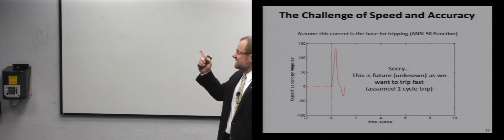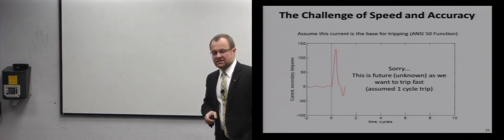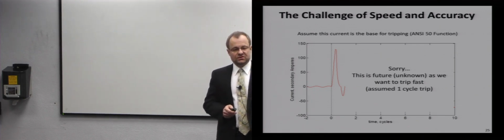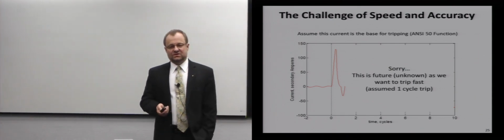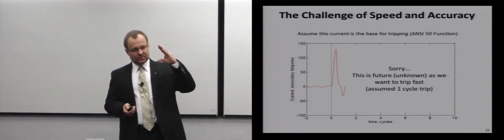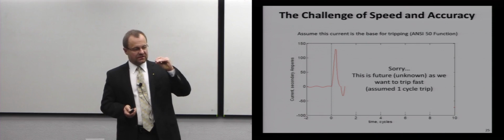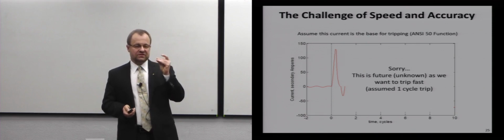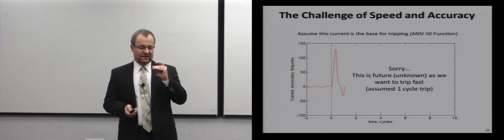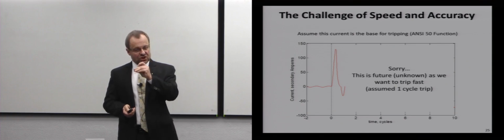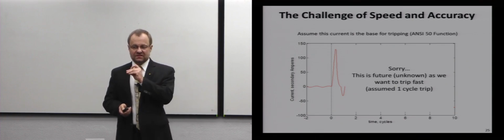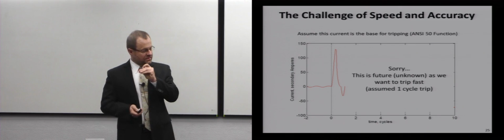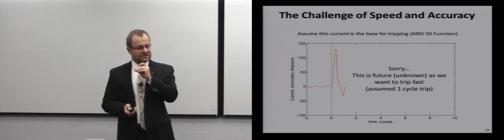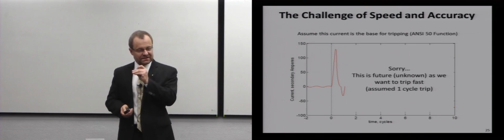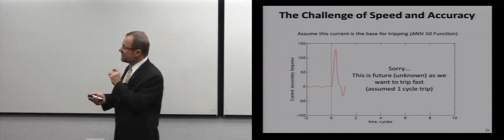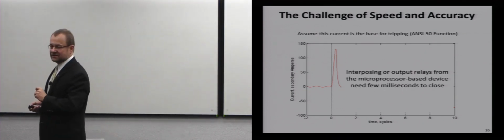So this is the data available to us, assuming that we will trip in one cycle. But guess what? To close that output, the little clicker in the relay needs 2 milliseconds to close. So in order to finish closing after 16 milliseconds, my microprocessor needs to issue a signal to it 2 milliseconds earlier. So I'm going to take away a little bit.